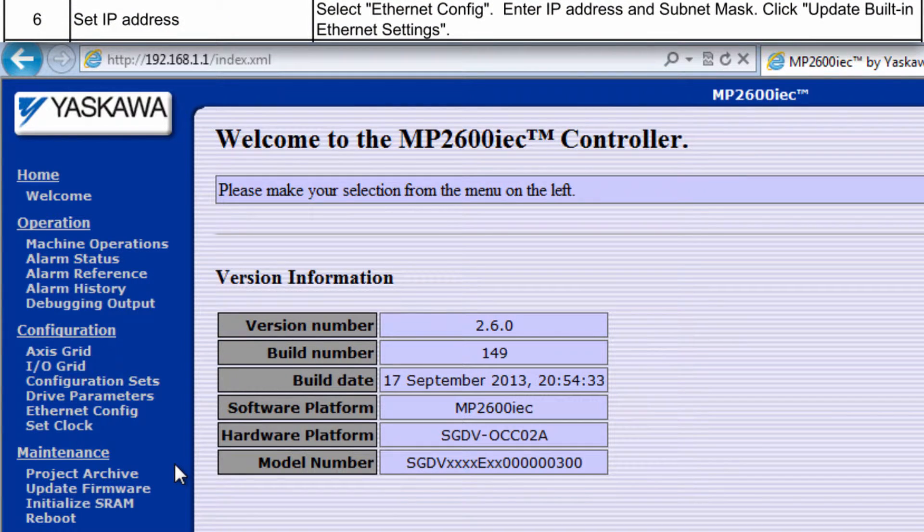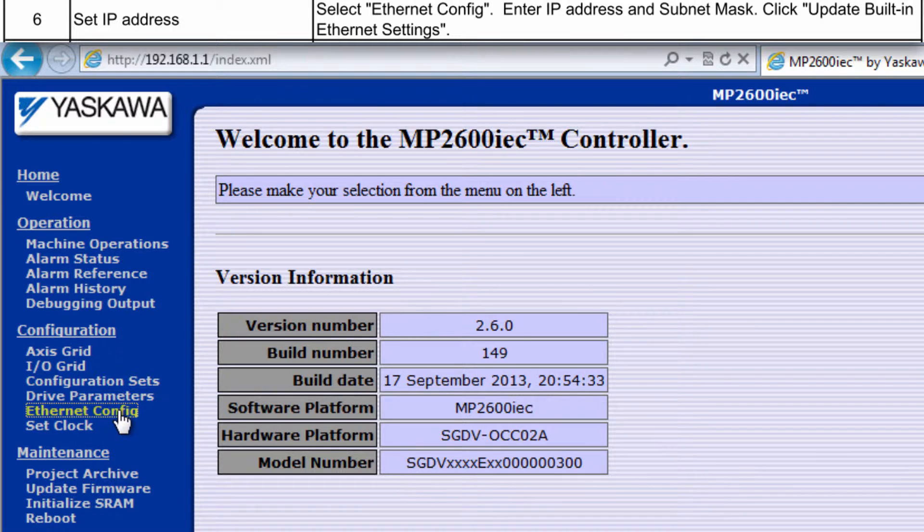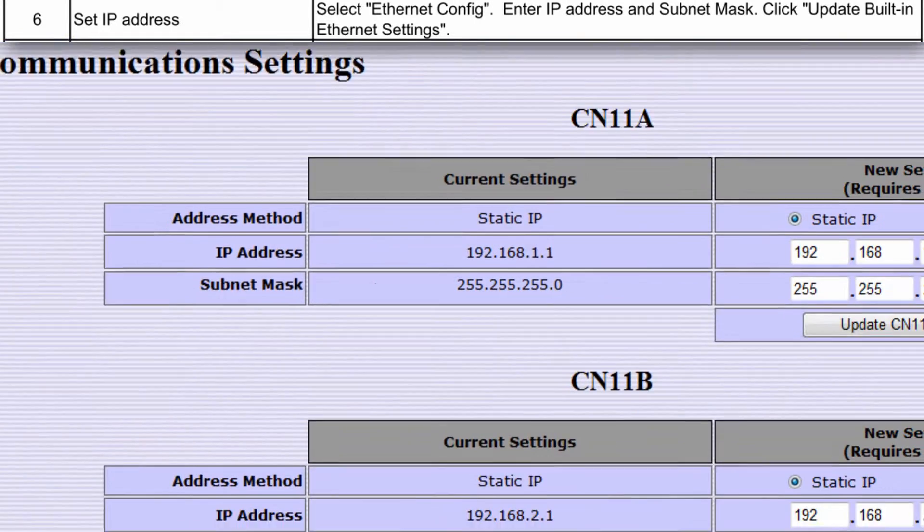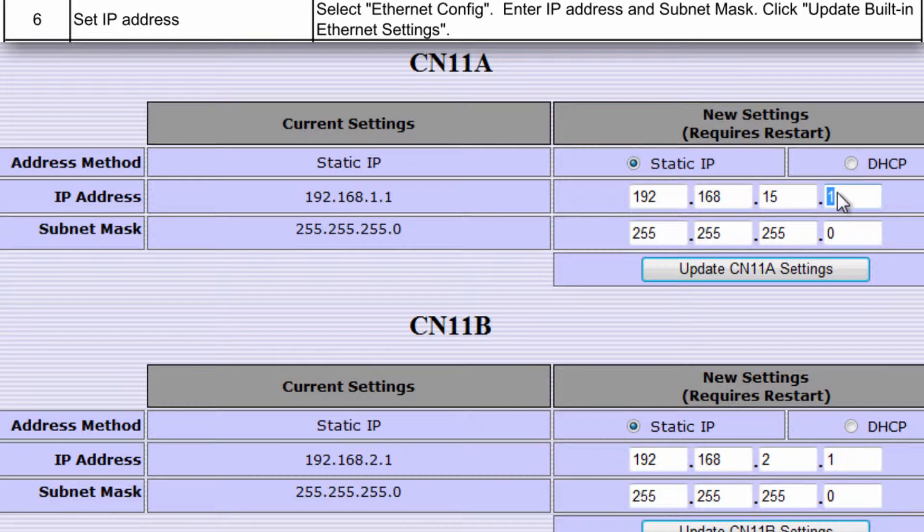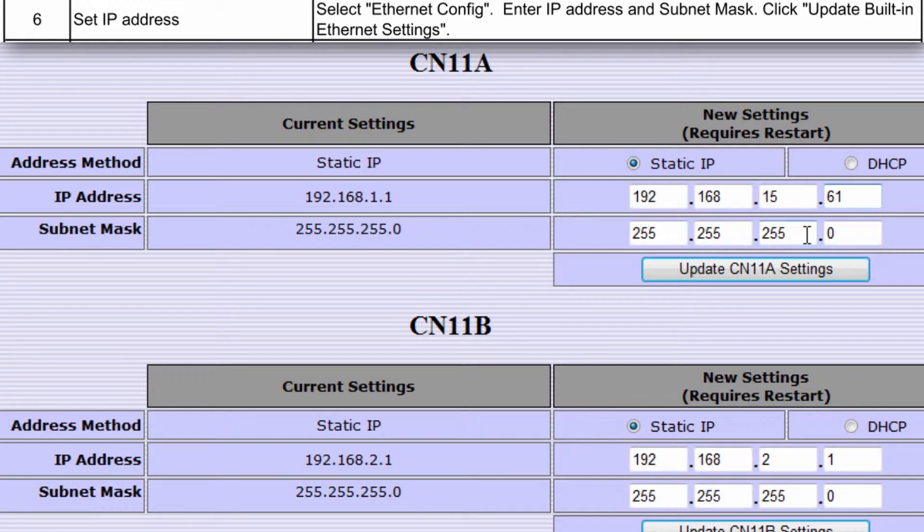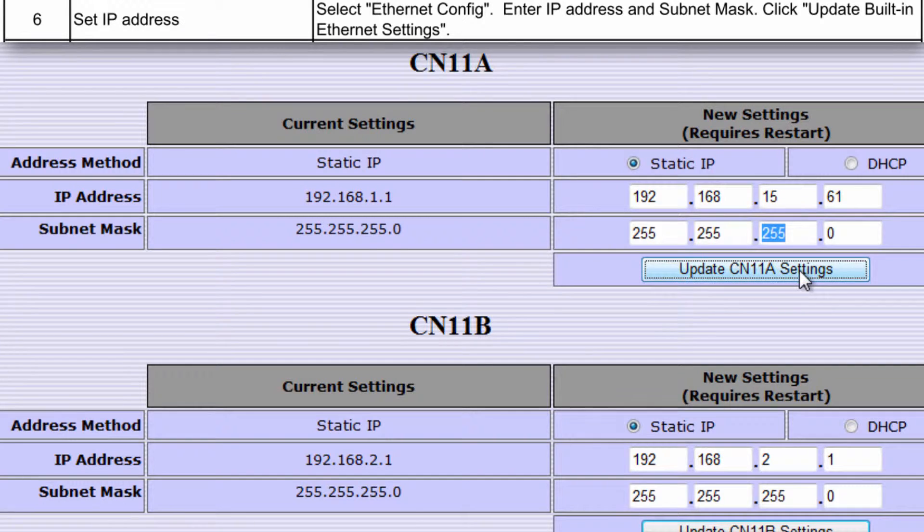Under Ethernet Config, enter the required IP address of the controller. It can be left at default, but I'll set this controller to 192.168.15.61. Leave the subnet mask at 255.255.255.0, and then click Update CN11A Settings.